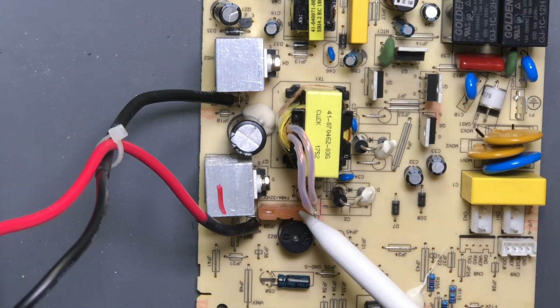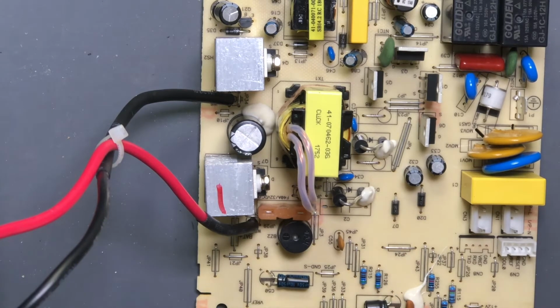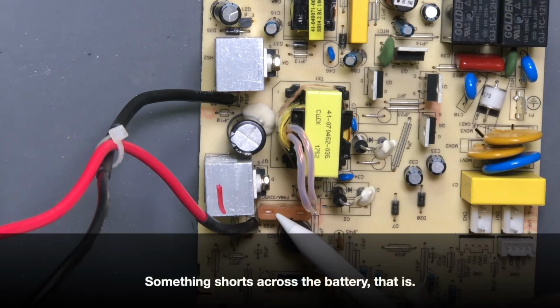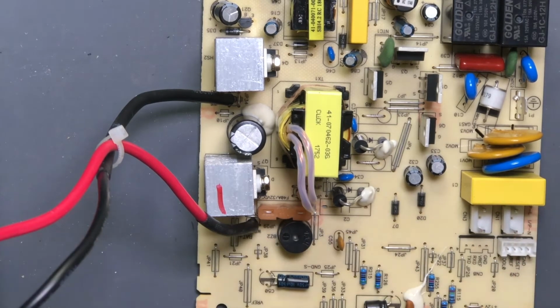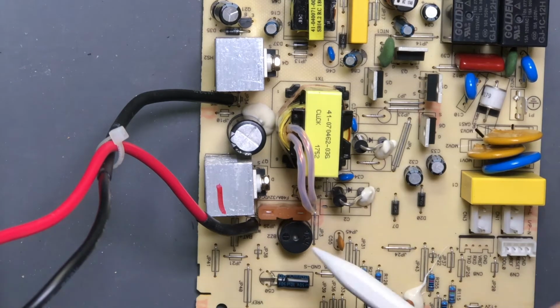When it's going full bore, it's going to be 20 to 25 amps. This fuse is to make sure that if there's a failure, the battery shorts, or something else shorts, it'll pop decisively. When it's disconnected from AC, the circuit breaker won't do anything since that's coming from the main, so you need something for the battery as well. But the battery is a limited supply to begin with; even fully charged, it only has so much energy in it.